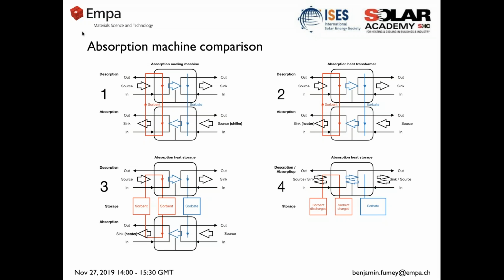We have a process where we need to be able to reach this maximum discharging in a single pass of the sorbent through the heat and mass exchanger. For this reason, we find that for liquid sorbents, the tube bundle falling film heat and mass exchanger as used for chillers and heat pumps is not ideal.